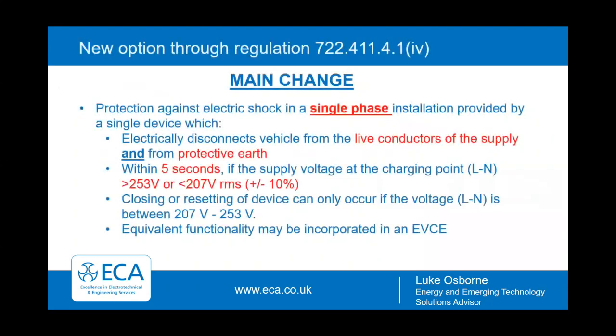So why is this? Well, the new option is in Indent 4 of 722.411.4.1. And this allows protection against electric shock for a single phase installation by a single device, which essentially monitors the nominal voltage, ensuring that it doesn't go outside of plus or minus 10% of the nominal voltage. And this has to operate within 5 seconds. So it will disconnect all the live conductors from the supply and also protective earth. And that's if the voltage between the live and the neutral goes above 253 volts or below 207 volts RMS. Obviously, this is likely to be incorporated into most electric vehicle charging equipment going forward.